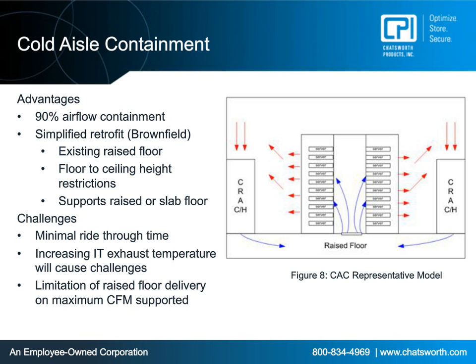The other limitation of a cold aisle is the CFM. Now, when you flood air into this space, if the servers are starting to ratchet up and draw more CFM, the floor tiles may not be able to keep up with the pace of how quickly the servers are pulling that CFM, or cubic feet per minute of air, that you need. So you could have a pressure imbalance, and the floor tiles, which are the limiting factor in my graphic here, could be stopping you dead, and then you've got a bigger problem.